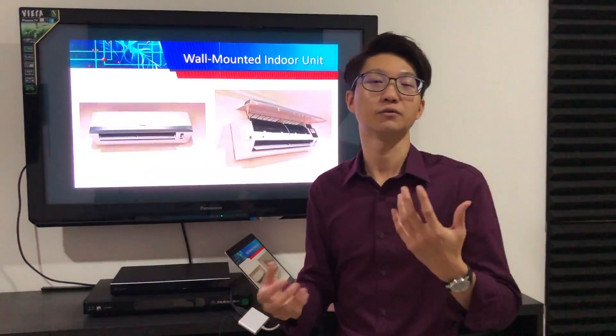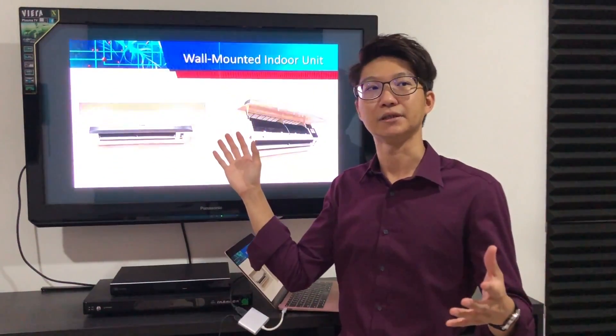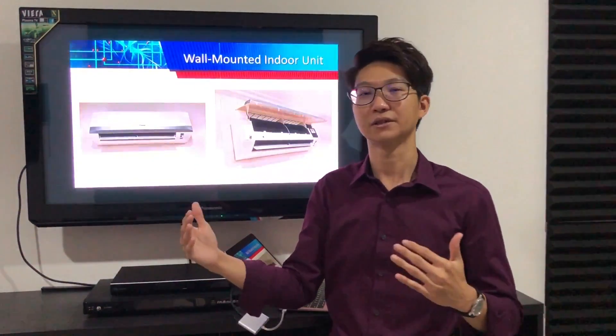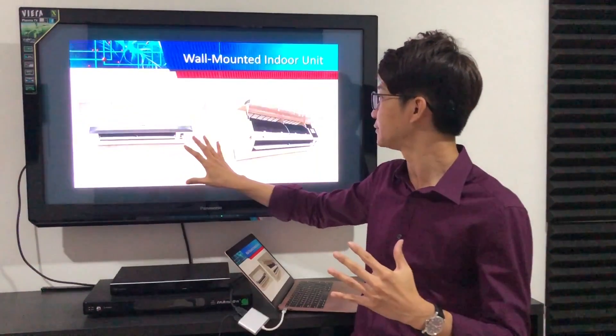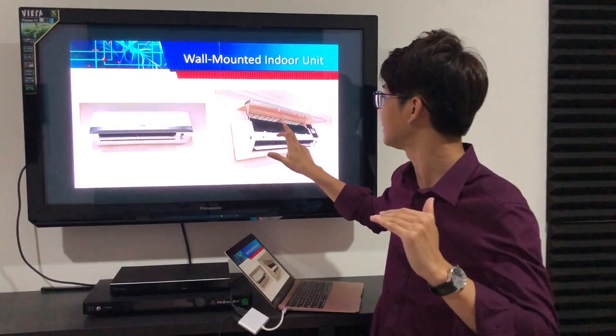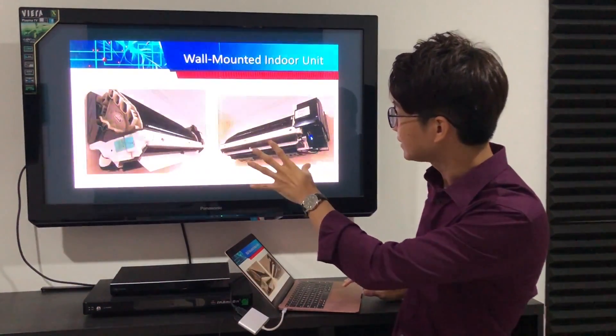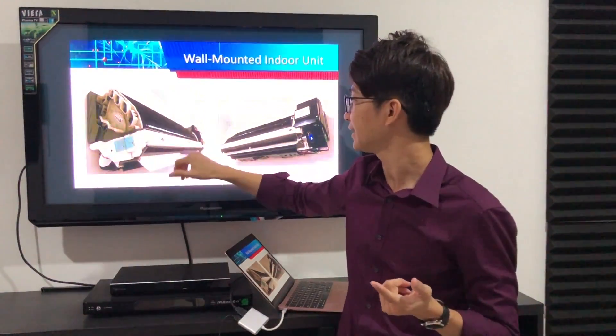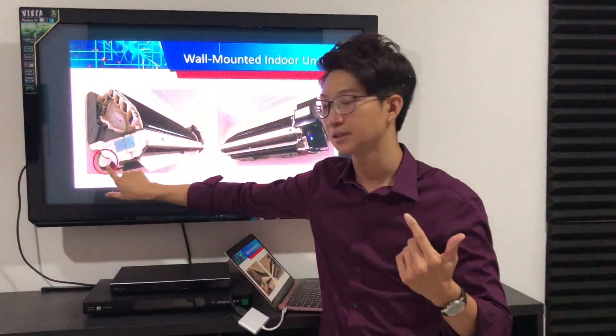When we talk about split or mini-split, the typical indoor unit is the wall-mounted unit. In Europe, people often just call it a wall-mounted air conditioning unit. This is the physical appearance — I'm sure many of us have seen this before. When you open it up, you can see the flap that opens when you turn it on, the basic plastic filter, and a fan blower. If we dismantle it, you can see the fin-tube heat exchanger and a tray for the drain water, with a pipe where the drain connects.